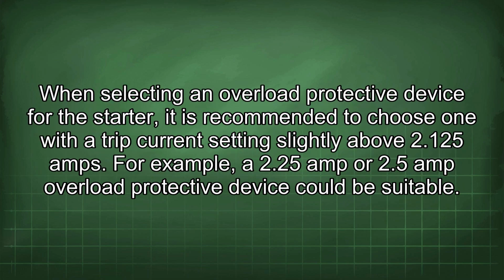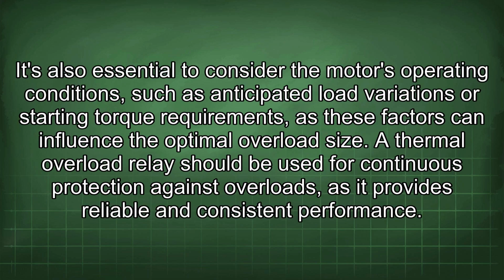When selecting an overload protective device for the starter, it is recommended to choose one with a trip current setting slightly above 2.125 amps. For example, a 2.25 amp or 2.5 amp overload protective device could be suitable. It's also essential to consider the motor's operating conditions, such as anticipated load variations or starting torque requirements, as these factors can influence the optimal overload size.